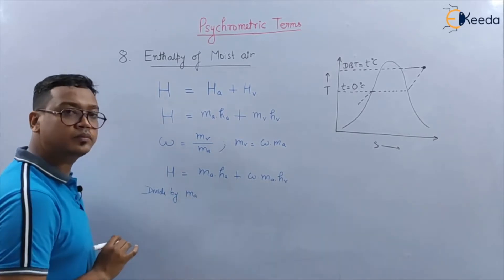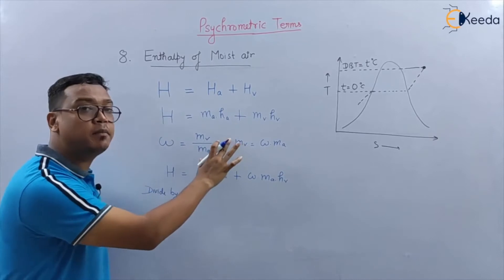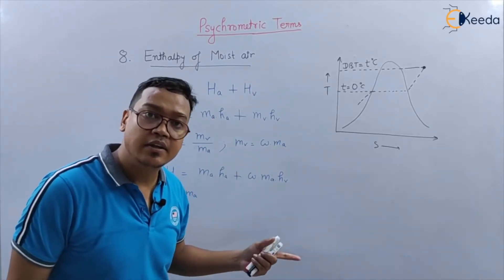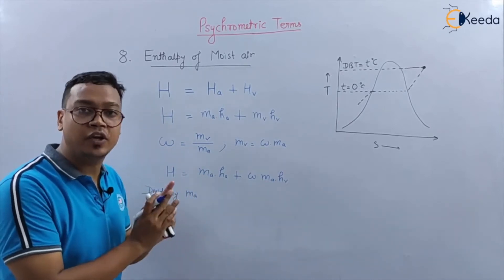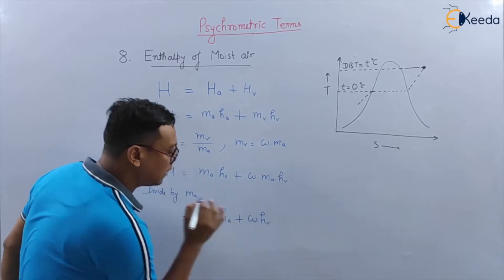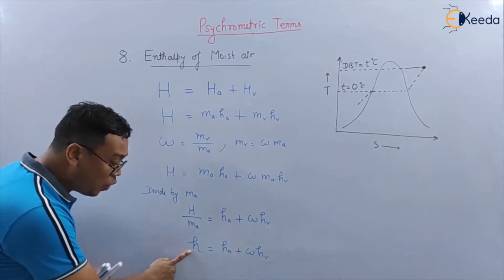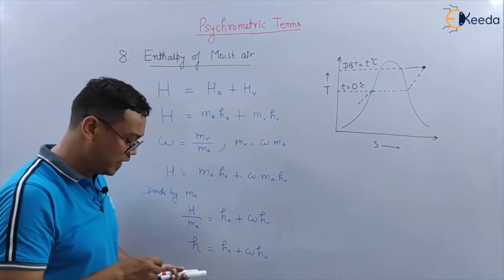I will divide this equation by MA. Listen very carefully to understand this property, because it is very important when doing load calculations or when understanding air conditioning processes. This is a very important property. So, small h — specific enthalpy — equals H divided by MA, which gives h equals HA plus Omega times HV. This is the total specific enthalpy of moist air, i.e., enthalpy of moist air per kilogram of dry air.